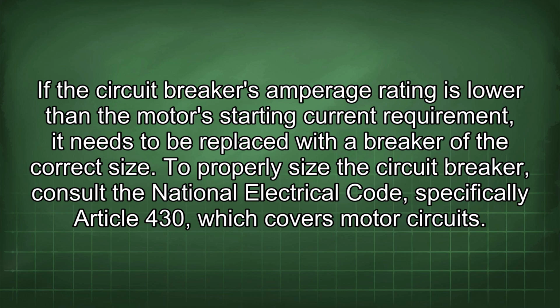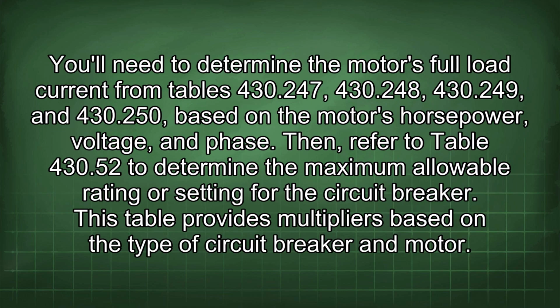To properly size the circuit breaker, consult the National Electrical Code, specifically Article 430, which covers motor circuits. You'll need to determine the motor's full load current from tables 430.247, 430.248, 430.249, and 430.250, based on the motor's horsepower, voltage, and phase. Then, refer to table 430.52 to determine the maximum allowable rating or setting for the circuit breaker. This table provides multipliers based on the type of circuit breaker and motor.